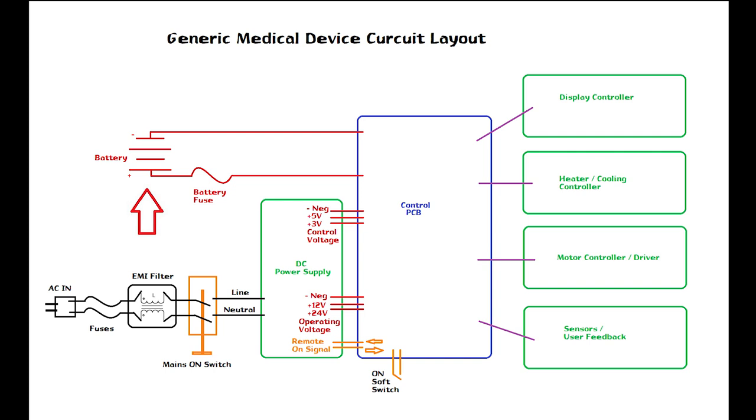Next, what you got to do is check the power on your battery. Because believe it or not, there's a lot of medical devices that actually run 100% off the battery, which means even if it's plugged in and charging, if it was completely down on the battery, it's got to sit there and it's got to charge for a little bit, kind of like your cell phone. Your cell phone is always running off the battery, so it has to charge up a little bit and then it will allow it to turn on. It does happen. So check your battery to make sure it's not fully depleted.